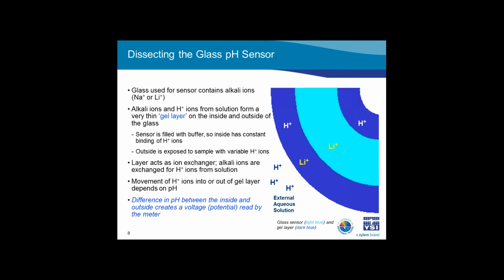The glass used to construct the sensing portion of the electrode contains alkali ions such as sodium or lithium. These ions, along with hydrogen ions in solution, form a very thin gel layer on the inside and outside of the glass. The gel layer is in dark blue on this image, while the glass pH sensor itself is in light blue. This layer acts as an ion exchanger of hydrogen ions, as alkali ions from the gel layer are exchanged for hydrogen ions from the sample. Therefore, depending on the pH of the sample, hydrogen ions will move into or out of the gel layer.